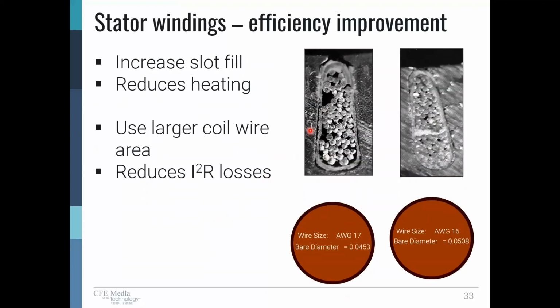In terms of the rewinding, one of the options or availability sometimes, here we see a winding on the left. You can see all the black air spaces, lots of room between wires, or air in between wires, that we could fill in with copper, with more wire. What we do is we don't change the number of turns in the coil, the number of times the wire goes around. We use bigger wire. So now what we would get is just an example on the right. We see the coils, the wires, we don't see much airspace between them. Because it's less airspace, bigger wire, we've got less losses from the larger wire and better heat transfer because there's smaller places for air pockets. Air is actually a good thermal insulator. So we want to minimize the air pockets, fill it in with varnish, but varnish isn't so good that it can fill large voids like that. And when we can go with larger wire, like the image shows, larger wire size, it's like a bigger pipe. We can put more water through it. We've got less losses by using a larger wire.